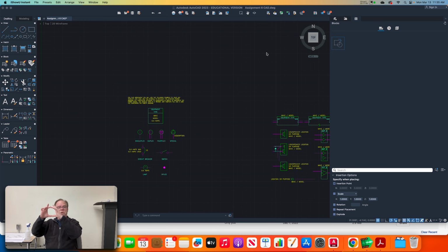Okay, and then what it's going to do is subdivide that. It's going to say, okay, we've got 4,000 amps in the building, and we're going to create a branch off of that that is 100 amps that goes this way, 100 amps available over here, 200 amps that goes this way, a couple hundred amps that goes this way. It's this little tree that branches off. And that 100 amp branch is going to be another panel that has a 100 amp breaker on it, okay? And inside that panel is going to be a whole bunch of smaller breakers, right? So in that 100 amp panel, you're going to have a 15 amp here, 15 amps there, 20 amps here, and so on until you get to 100, okay?